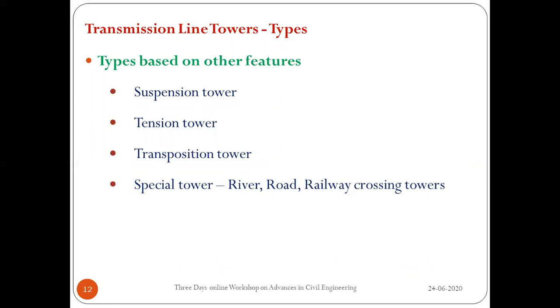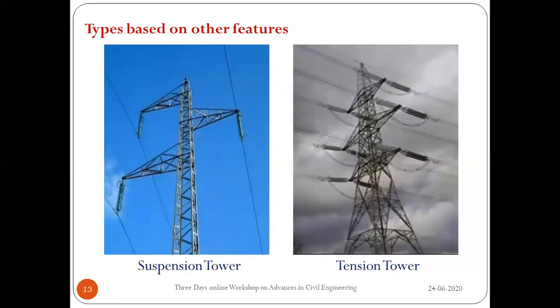Tower types based on other features: depending upon the hanging of insulators, towers are called suspension or tension towers. In a suspension tower, the insulator is hung freely from the tip of the cross arm. In a tension tower, the insulator is placed horizontally and participates in tension. Transposition towers are an electrical requirement where the R, Y, B phases are rearranged. Special towers such as river crossing, railway crossing, road crossing, and communication line crossing towers have increased height and design requirements.